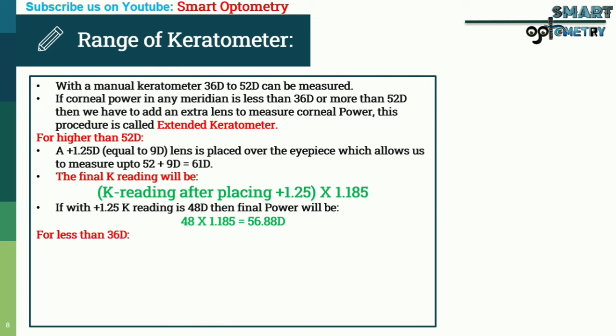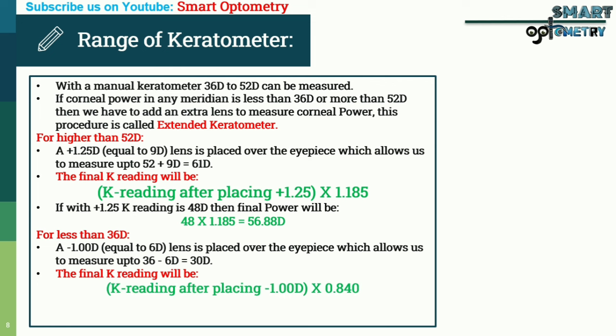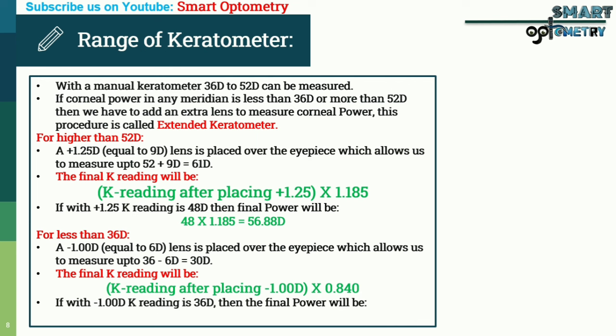For less than 36 diopters, a -1 diopter lens (equal to 6 diopters) is placed over the eyepiece, allowing measurement down to 36 - 6 = 30 diopters. The final keratometry reading = reading after placing -1D lens × 0.840. For example, if with -1D the reading is 36 diopters, the final power = 36 × 0.84 = 30.24 diopters.